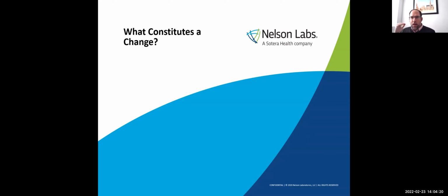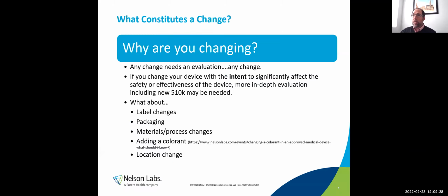And the first thing to always think about is, what do we consider a change? What incorporates a change to you as a medical device manufacturer that you should be considering for biocompatibility? So the first thing I always say is, why are you changing? I always make fun of marketing departments when we look at changes, because sometimes people want to change a device just to change a color, or they think they can sell more if they change something that's not really functional or beneficial to the patient. And I always, as a risk assessor and as a biocompatibility expert, cringe, because for me, any change should be a benefit to the patient. It shouldn't just be a change for the sake of change.